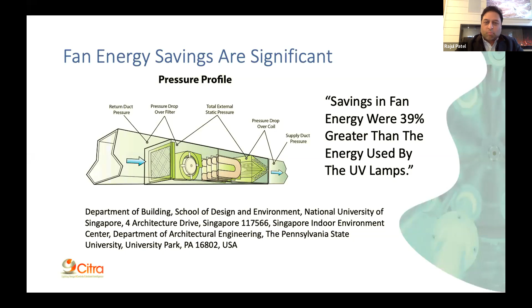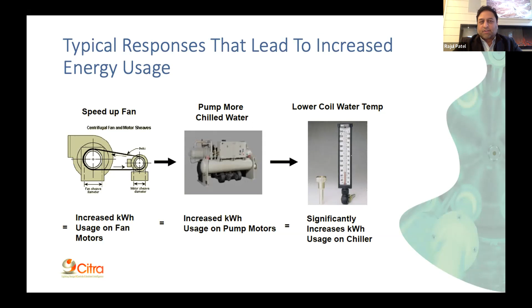And these are some common responses that facilities may take as the system becomes more inefficient due to the biofilm. You speed up the fan, you pump more chilled water, you lower the coil temperature, all of these actions trying to achieve the cooling temperature, but you're also increasing energy use.